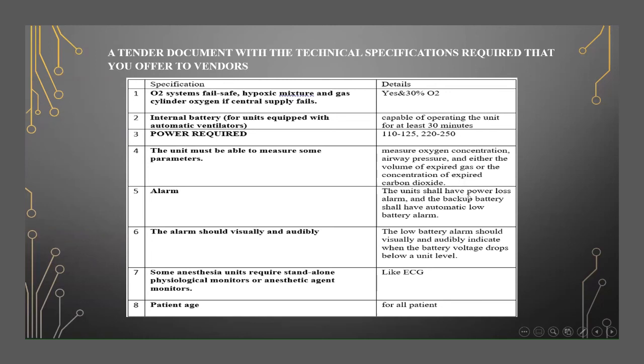Alarm: the units should have a power loss alarm, and the backup battery should have an automatic low battery alarm. The alarm should be visual and audible. The low battery alarm should visually and audibly indicate when the battery voltage drops below a unit level. Some anesthesia units require standalone physiological monitors or anesthetic agent monitors, for example ECG. Patient age, we have for all. We want to make the anesthesia machine for all patients.